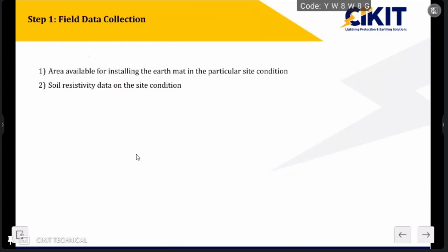So the first step is field data collection. The first thing is we need to visit the site and check what is the available area for this earth mat conditions. If you take this substation, earlier it was open space where a lot of space was available, but nowadays there are so many constraints on space availability. So first we have to go to the site and check what is the space availability for installing this earth mat. And the second important thing is the soil resistivity.